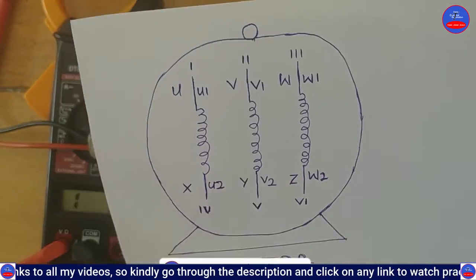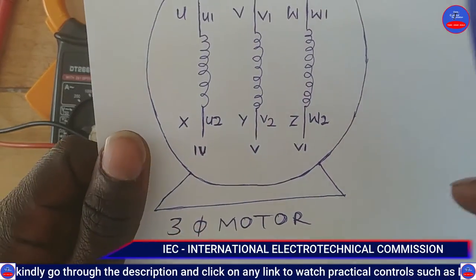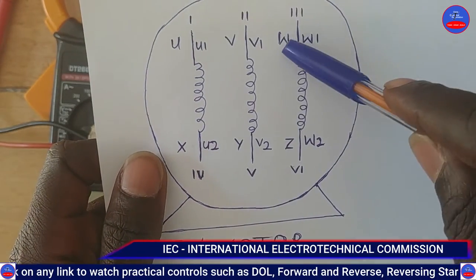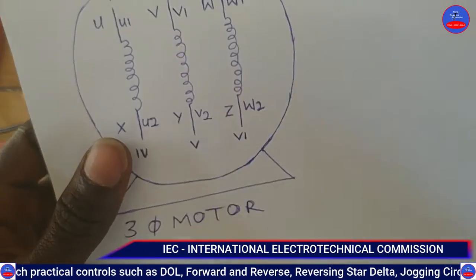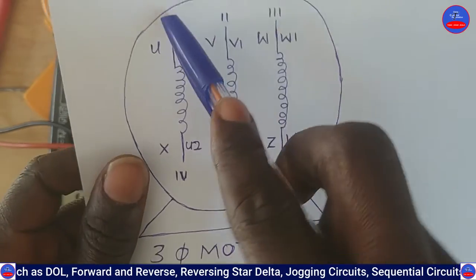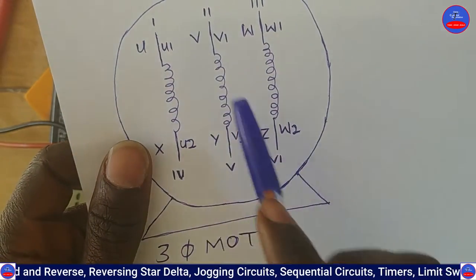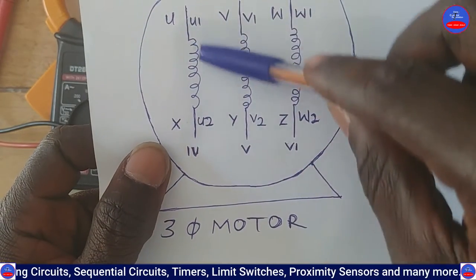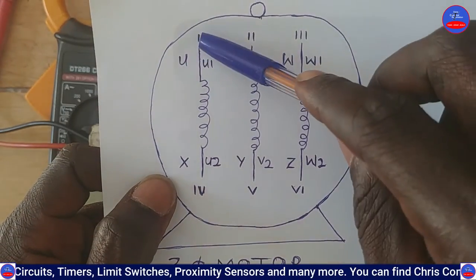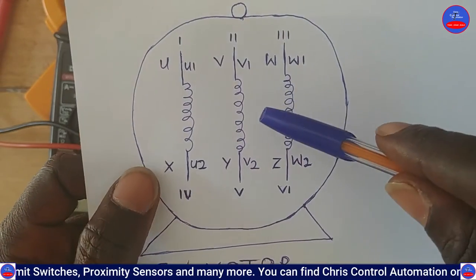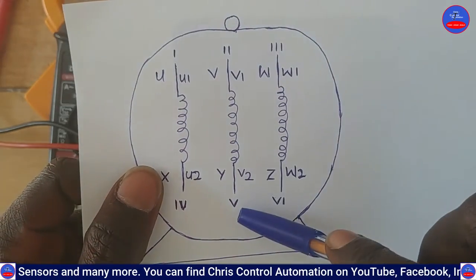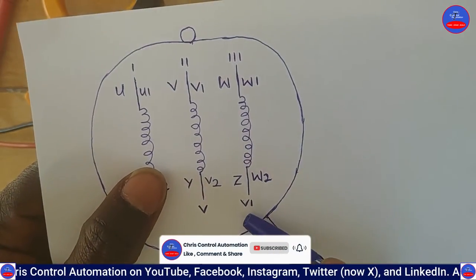Those markings — U/X, V/Y, W/Z — are commonly used by European countries. IEC, the International Electrotechnical Commission, specifies these values. Sometimes when motors are sent for rewinding, they also use Roman numerals. For this winding you have I and IV — that is one and four. Then II and V — that is two and five. And III and VI — that is three and six.